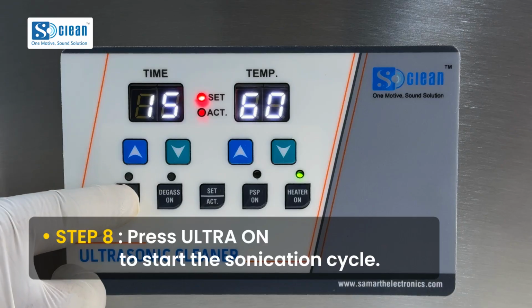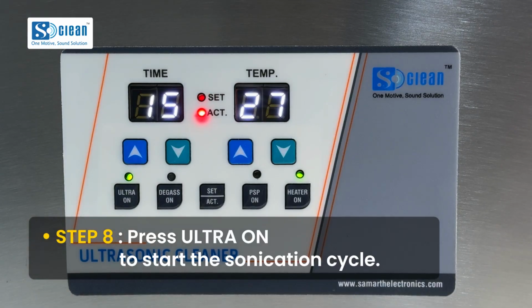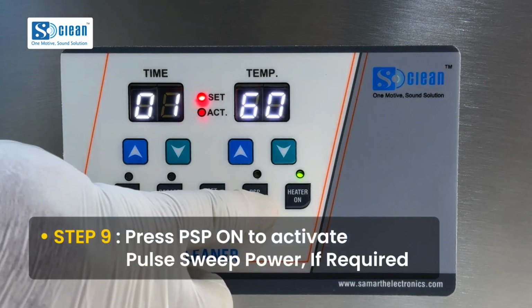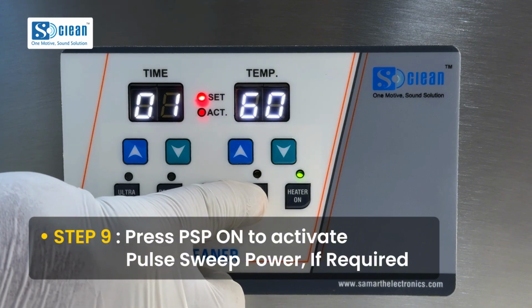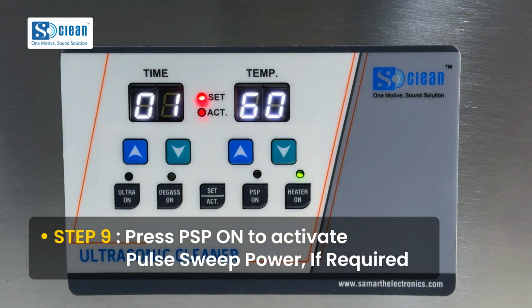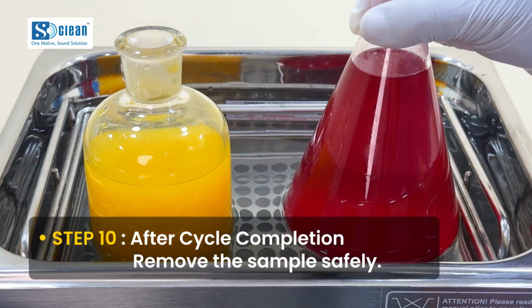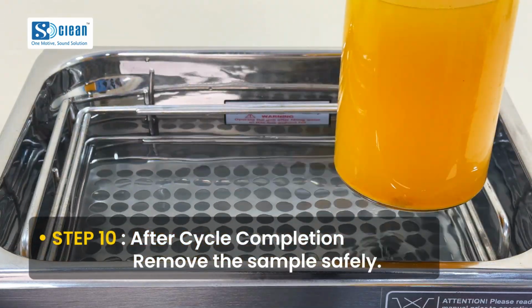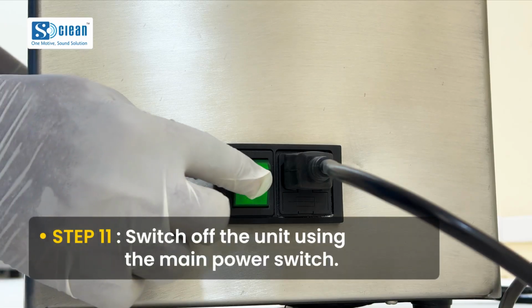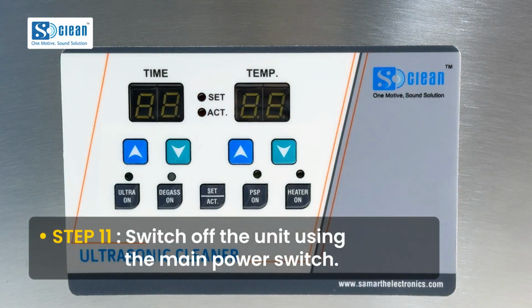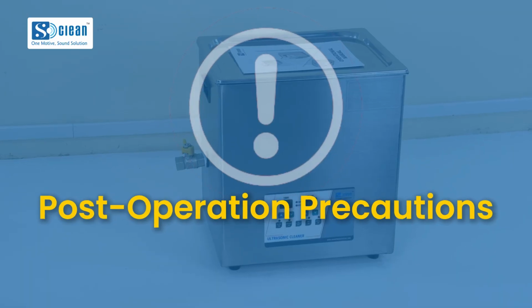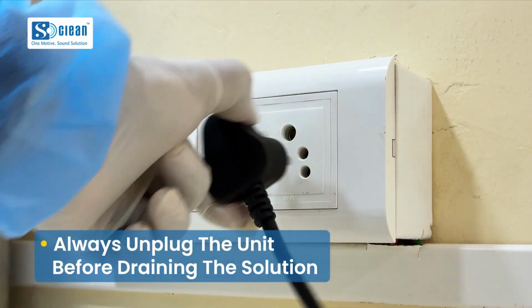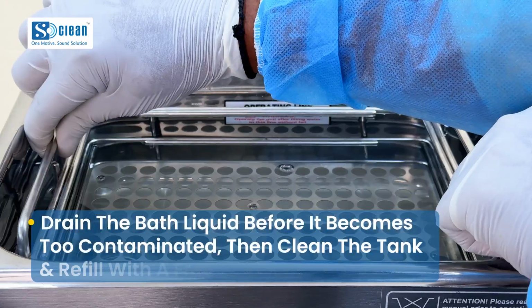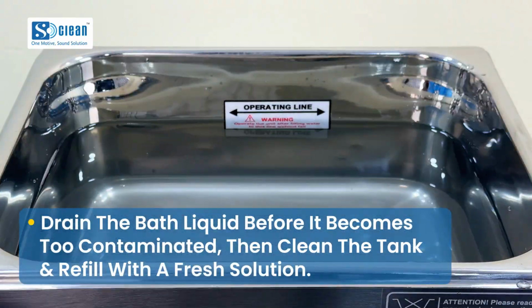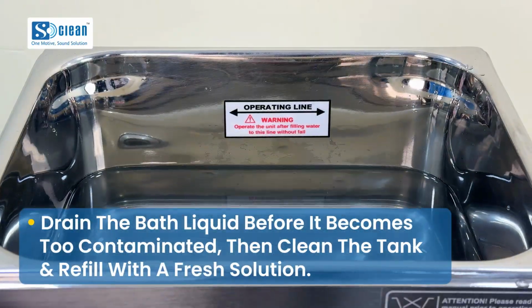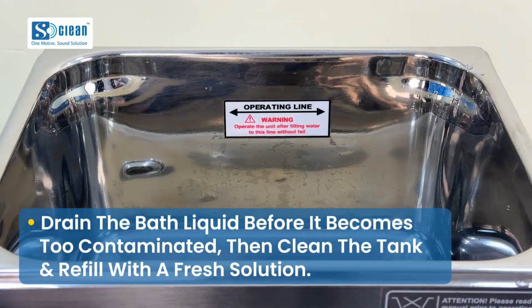Step 8. Press ultra on to start the sonication cycle. Step 9. If required, press PSP on to activate pulse sweep power. Step 10. After cycle completion, remove the sample safely. Step 11. Power off. Switch off the unit using the main power switch. Post-operation precautions. Always unplug the unit before draining the solution. Drain the bath liquid before it becomes too contaminated. Then clean the tank and refill it with a fresh solution.